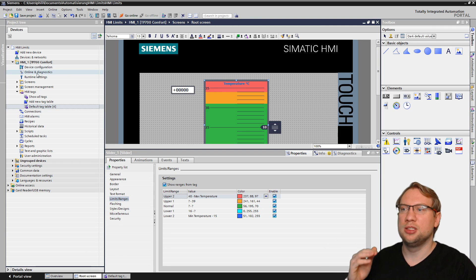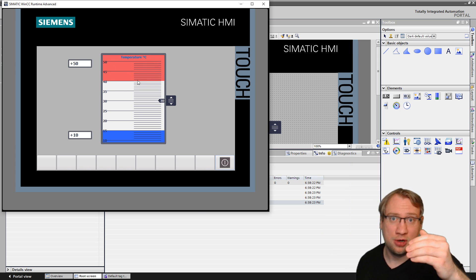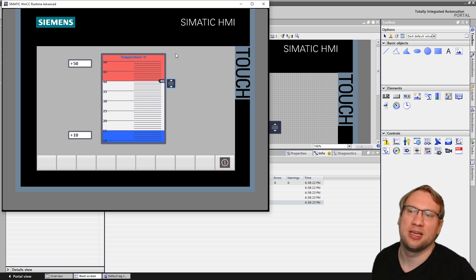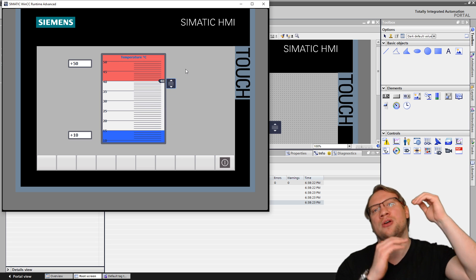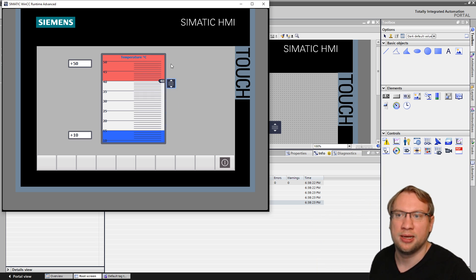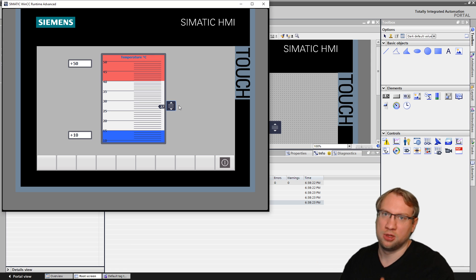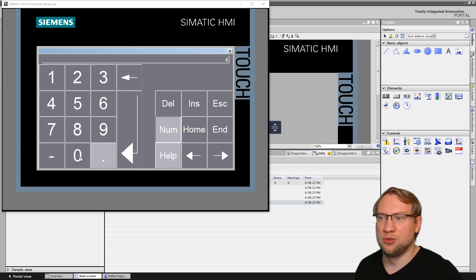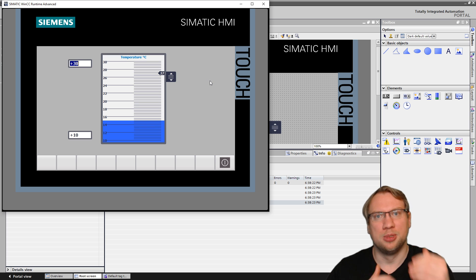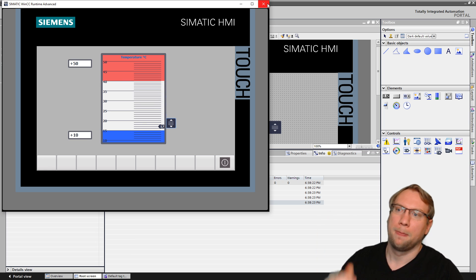Now in the simulation you can already see upper two and upper one displayed. With the slider itself I cannot go into those danger areas — they exist for error scenarios where the PLC or calculations might drive the value there, but the slider enforces the limit. That's the limit for the slider, which makes a lot of sense. For the bar graph it makes even more sense visually. If I set the maximum to 30, I can't even see the range anymore — so you'd usually leave it with the ranges visible.